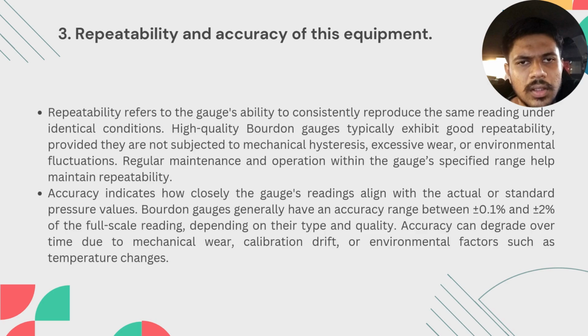Okay. The third question, repeatability and accuracy of the experiment. Repeatability refers to the gauge's ability to consistently reproduce the same reading under identical conditions. High quality Bourdon gauges typically exhibit good repeatability, provided they are not subject to mechanical hysteresis, wear, and environmental fluctuation. Regular maintenance and operating within the gauge's specified range help maintain reliability.